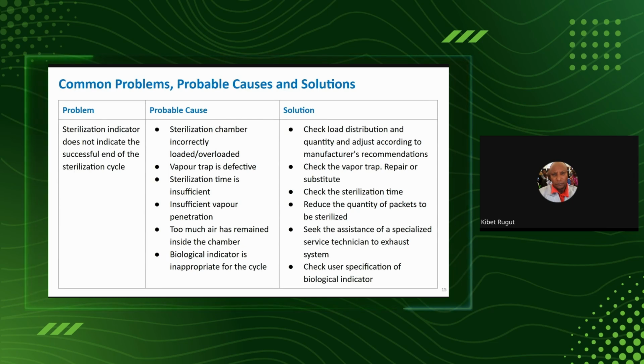Now, in troubleshooting, I may not explain all of the problems, but we have just summarized a chart of the probable causes of problems that you come across in autoclaves, and their proposed solutions. This may not be the perfect book, but it is common. So the sterilization indicator does not indicate the successful end of the sterilization cycle. Of course, the machines are programmed to make sure everything is sterilized. So if something has not been attained, it will not cheat, it will not lie.